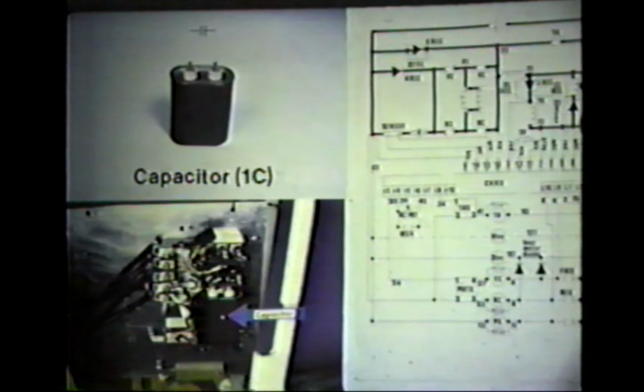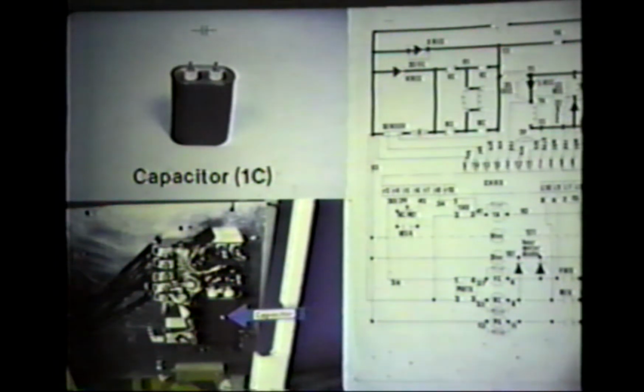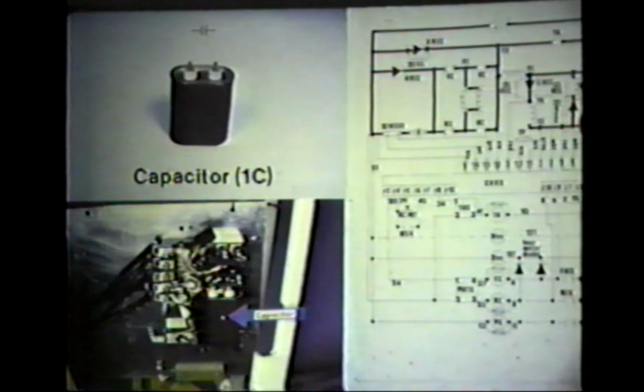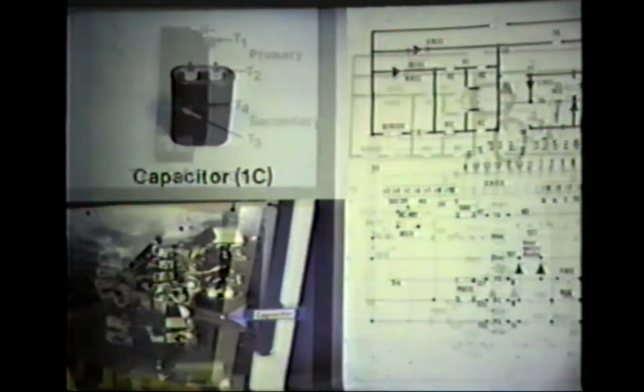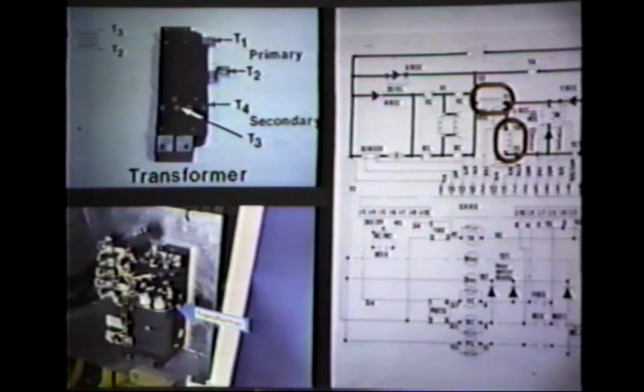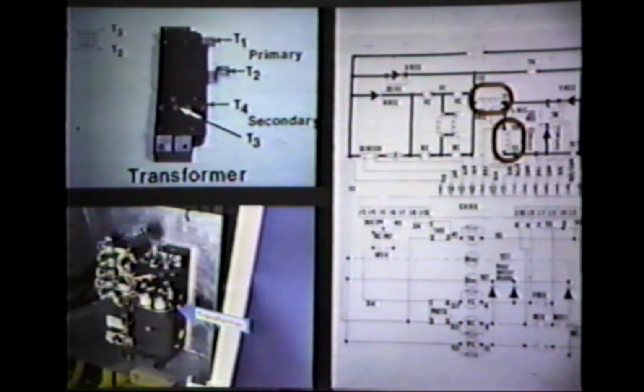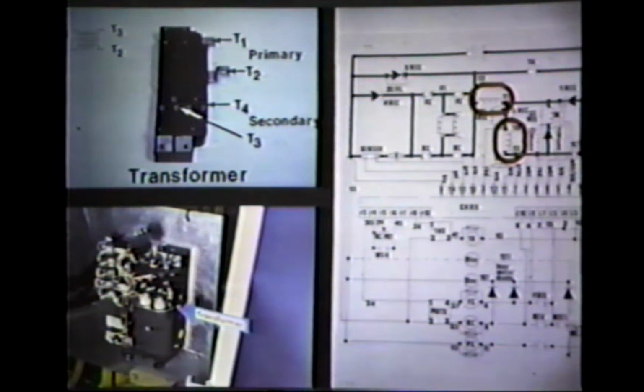The capacitor 1C is mounted adjacent to the 1-rec. Before working on the electrical system, always unplug the battery and discharge the capacitor by shorting a metallic object across the capacitor terminals. Beneath the capacitor lies the transformer, which also serves as the mounting block for the 2 and 5 recs and the snubbers. Note the terminals for the primary winding T1 and T2 and the secondary windings T3 to T4.